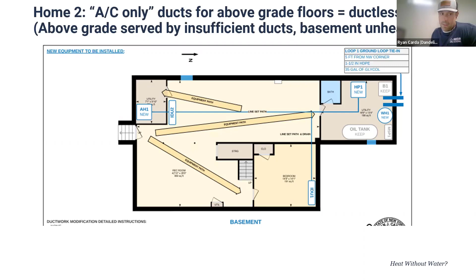Example number 3 is also a nice application for VRF. This home had 2 different systems, forced air on the main floor and basement, and a separate system on the second floor. The entire load for this home was less than 5 tons, so we could easily cover it with a single compressor unit. We tied that to 2 separate air handlers, one in the attic for the second floor, one in the basement for the first floor and the rest of the house. Before VRF, this would have required a package unit in the basement plus a split unit serving the second floor ductwork. Condensing this to a single heat pump served by 2 air handlers let us reduce costs for this customer.